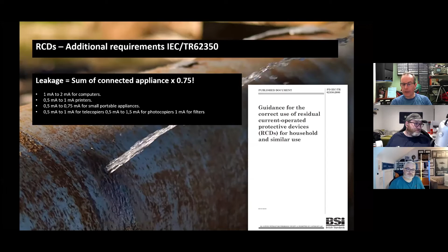Okay, so leakage currents, staying on leakage currents. This one I have left in because I thought we'd wind this up on real controversy. And real controversy is this. This has been deleted by BS 7671, Regulation 543.7.1.201. It was UK specific. Equipment having a protective conductor current exceeding 3.5 milliamp but not exceeding 10 milliamp shall be permanently connected to the fixed wiring of the installation without the use of a plug or socket outlet, or connected by means of a plug and socket complying with 60309-2.